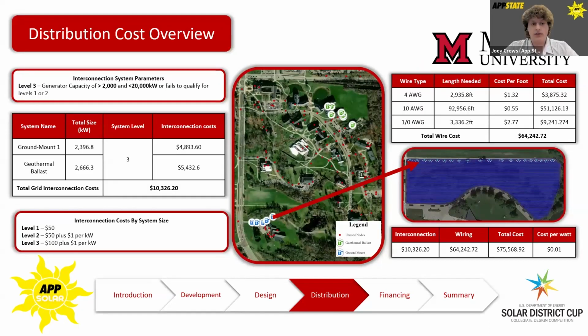For distribution costs, our main considerations were interconnection costs and wire sizing. The inverters are placed at the end of the arrays to optimize future maintenance and space. This also minimizes the system's voltage drop and wiring costs because the wires used for PV stringing on the DC side are much smaller. As you can see by the table at the bottom right, these changes have minimal effects on the bottom line, but are still important considerations.